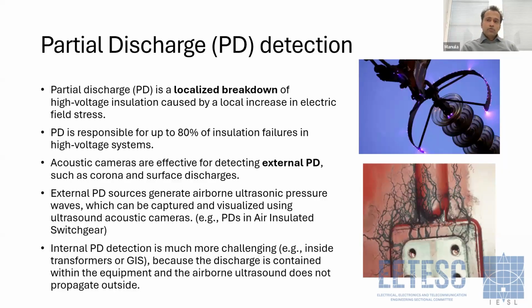So these discharges would produce ultrasound. Other than that, there might be ultraviolet rays and other signals as well. But in our application, it would produce ultrasound that can be detected by using ultrasound cameras. It is a known fact that partial discharges are responsible for about 80% of insulation failures in high voltage systems. So in failures of high voltage systems, partial discharge would account for 80% of the failures.